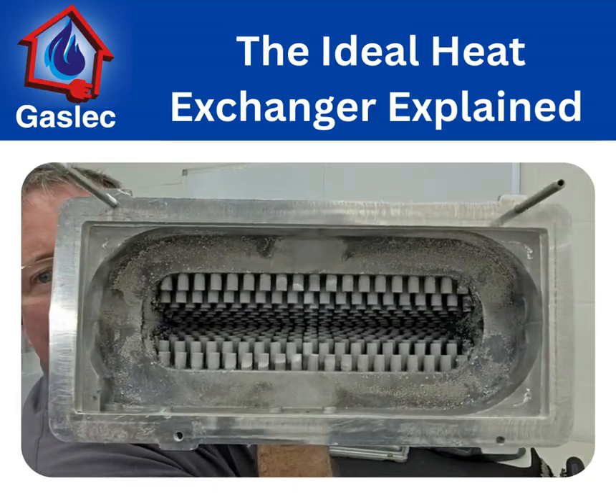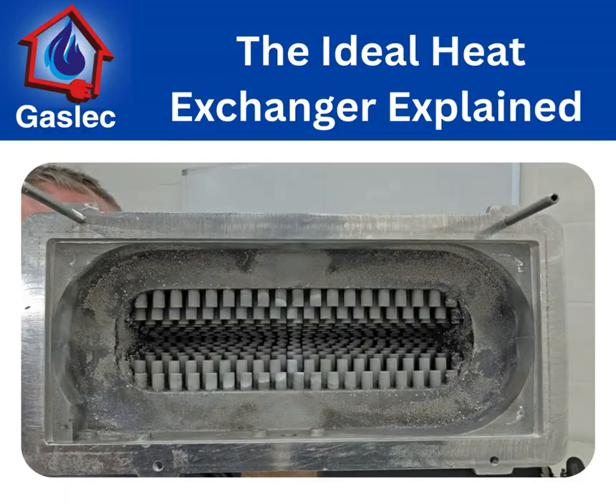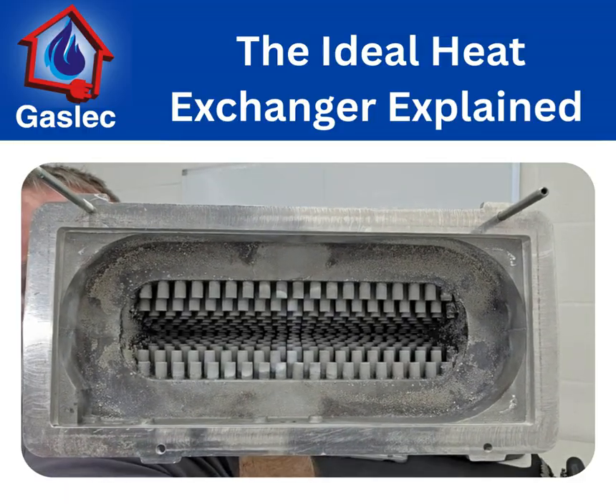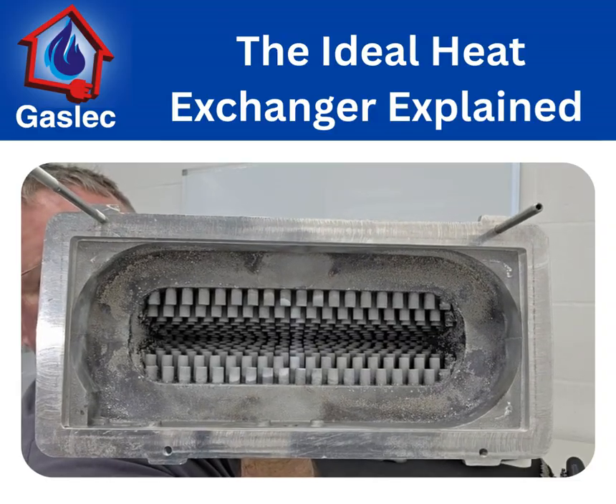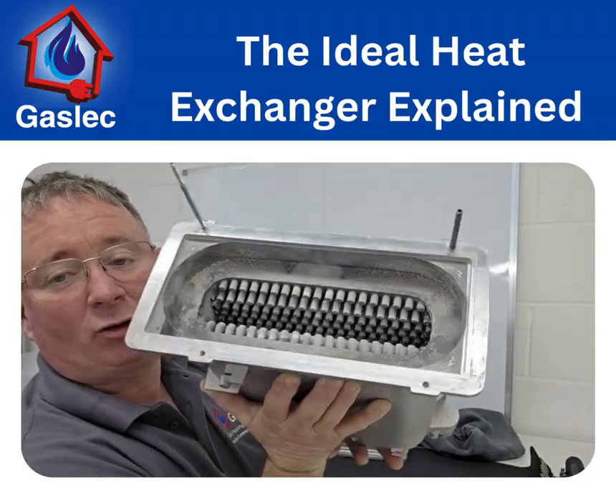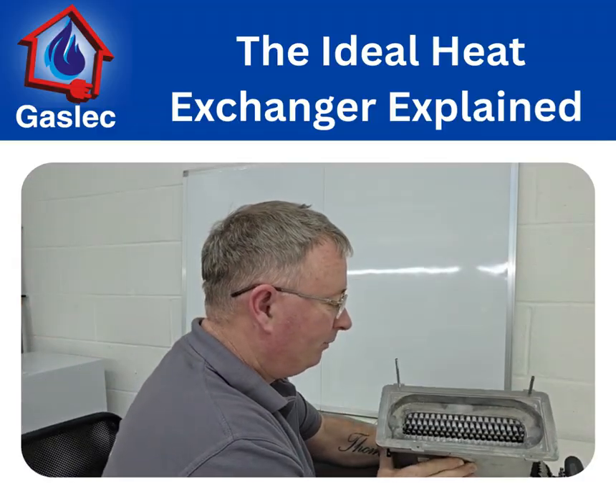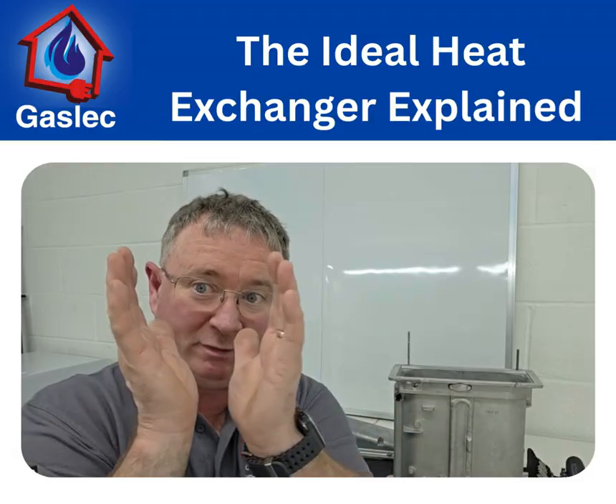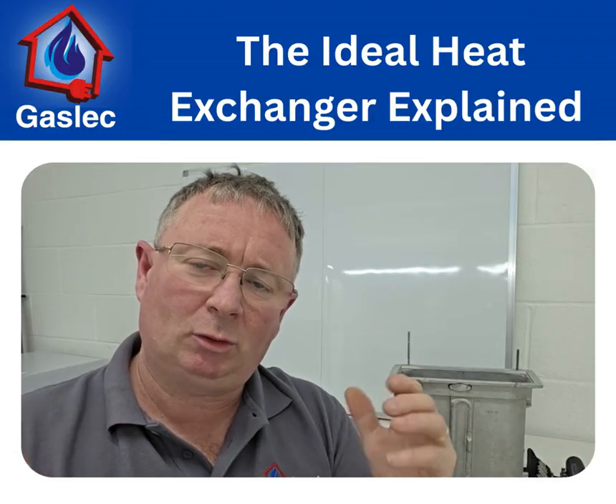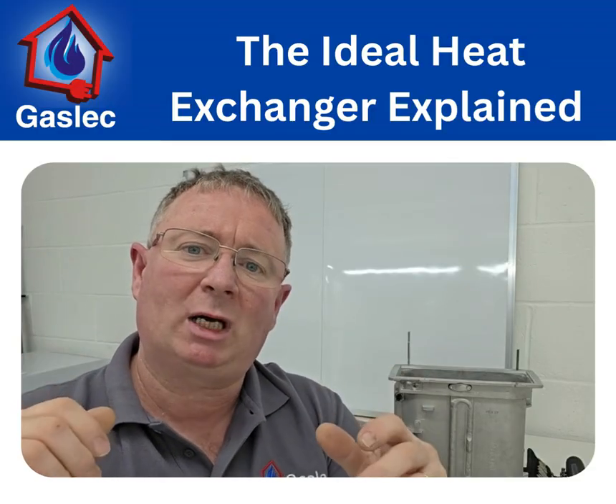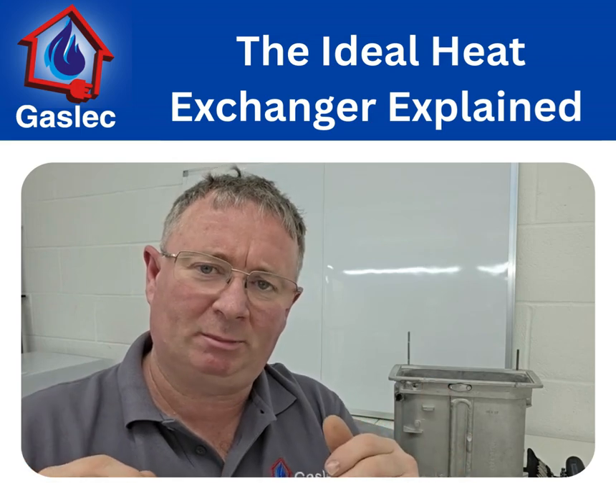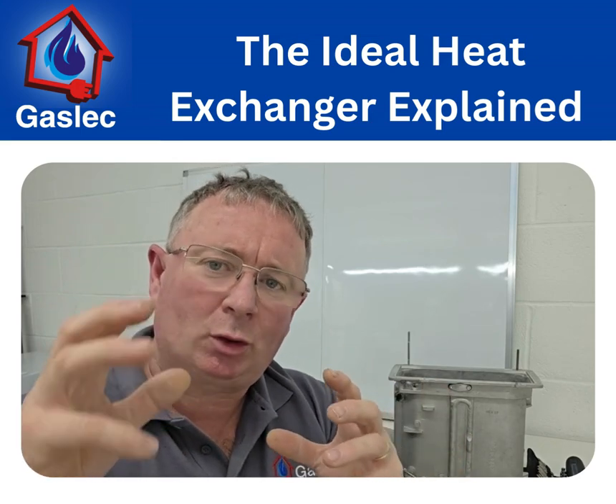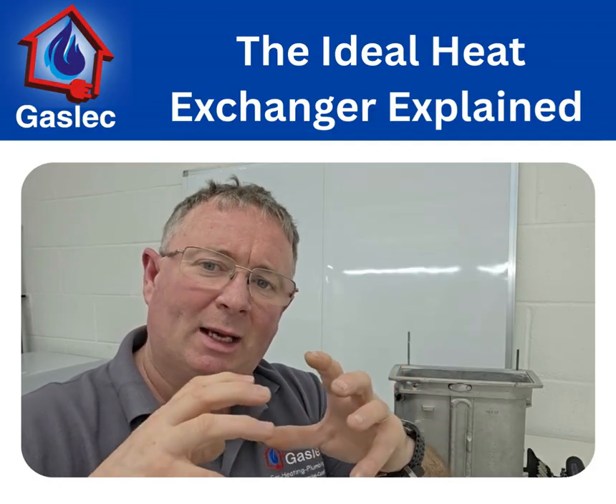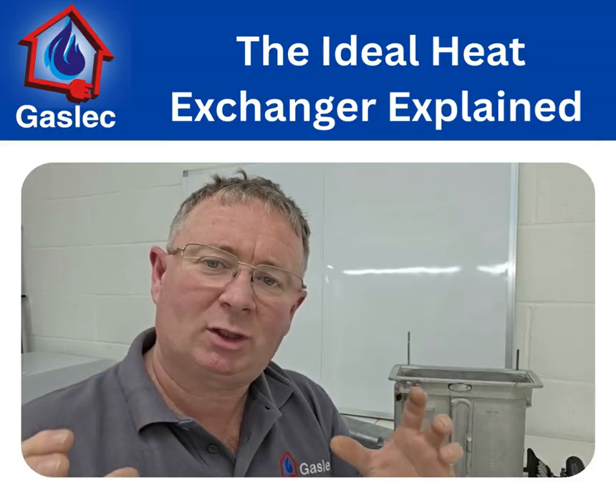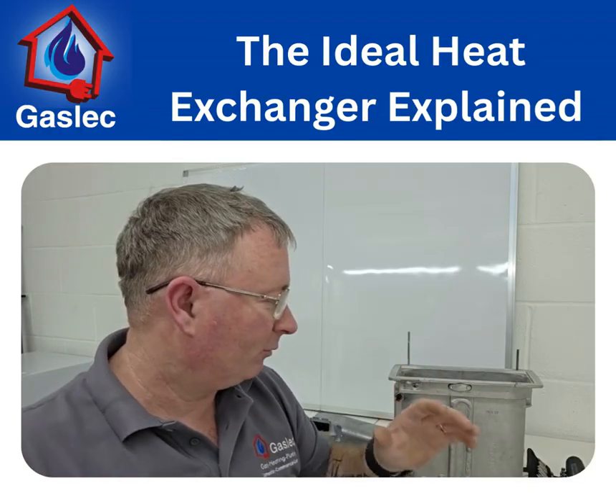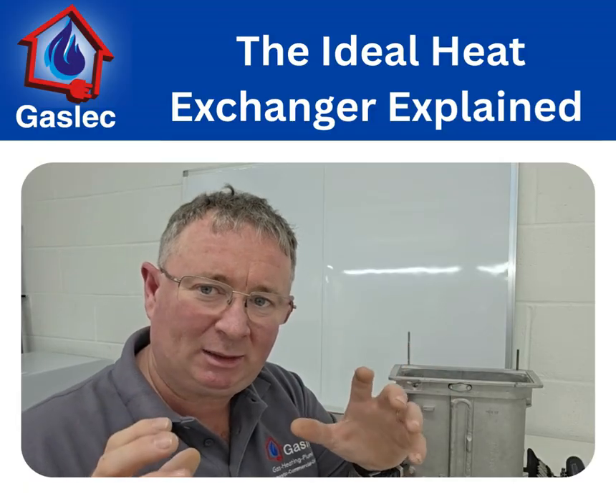So that is the inside of the heat exchanger, and we can see those little, I'm not sure what you call them, those little circular teethy things that catch all of the heat and transfer it to the water. But they narrow into a V shape. Now if your heat exchanger starts getting blocked up with little bits of carbon deposits from the combustion process, we start getting hot spots inside the heat exchanger, and that can cause distortion and the heat exchanger to start warping, and we don't want that. So for the longevity of the heat exchanger, we need to keep it clean.